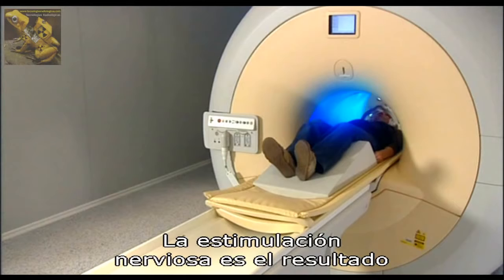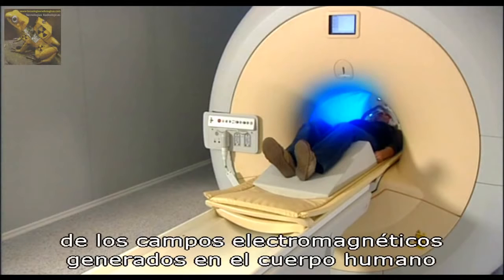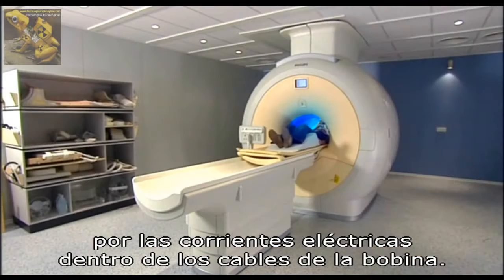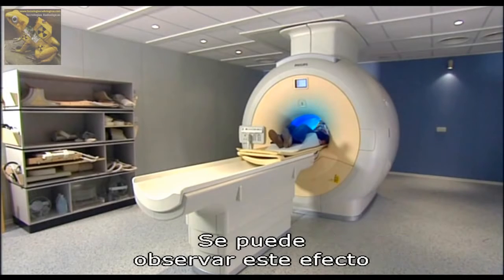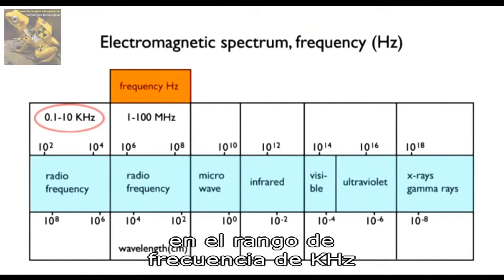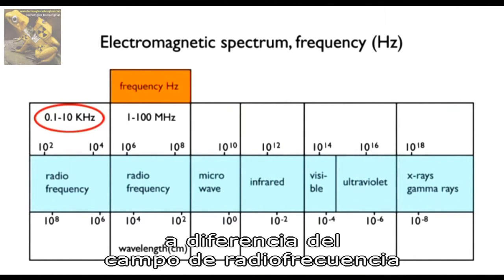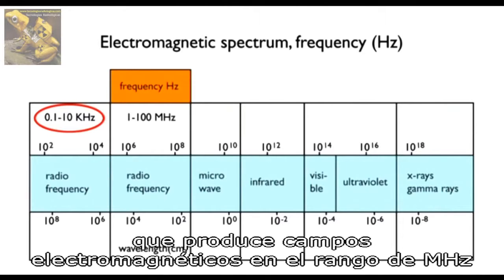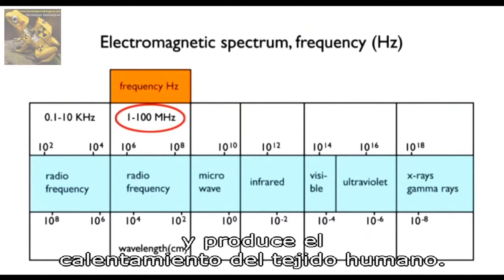The nerve stimulation results from the electromagnetic fields generated in the human body by the switched electric currents in the copper leads of the gradient coil. This effect is observed in the kilohertz frequency range, as opposed to the RF system which produces electromagnetic fields in the megahertz range and results in heating of the human tissue.